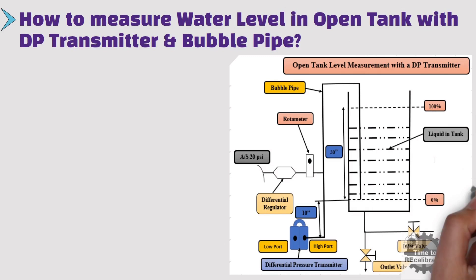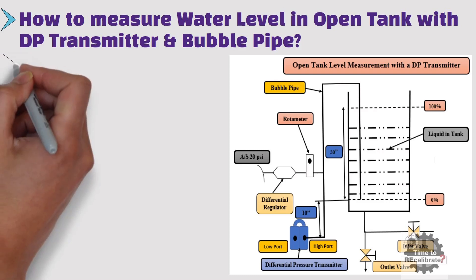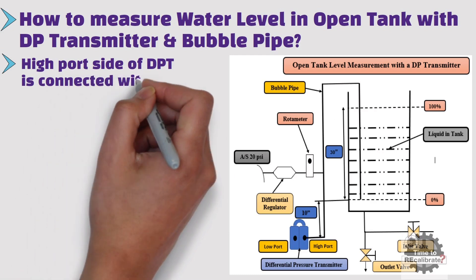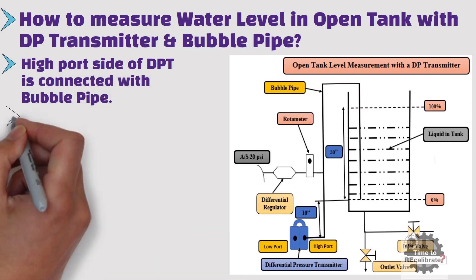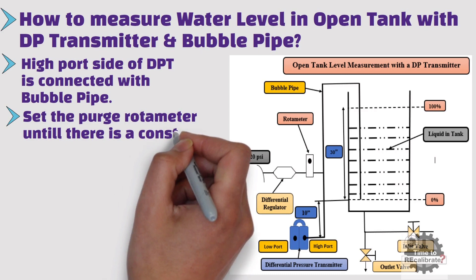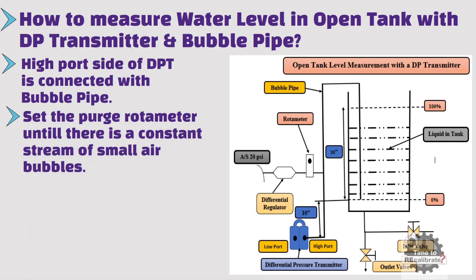As you can see from the picture, the differential pressure transmitter is installed 10 inches below from the minimum level of liquid in the tank. The high port side of the DPT is connected with the bubble pipe. Set the purge rotameter until there is a constant stream of small air bubbles. Because of the bubble pipe, transmitter position does not affect the calibration range, and we can neglect transmitter installation.